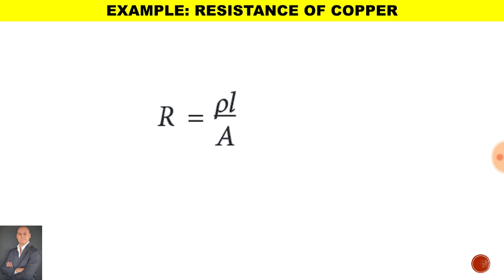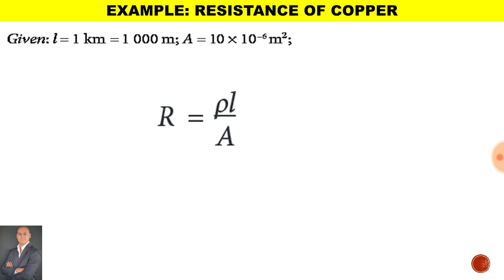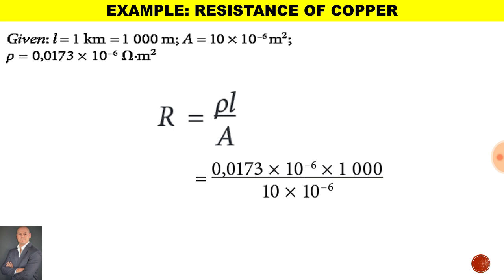Our next example is to calculate the resistance of copper. We've been given a length of one kilometre of copper conductor, which means it is 1000 metres. The cross-sectional area of the copper cable is 10 times 10 to the minus 6 metres squared, and the resistivity is 0.0173 times 10 to the minus 6. Substituting those values, we get a resistance of 1.73 ohms.